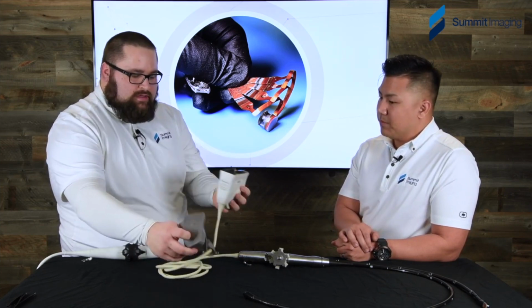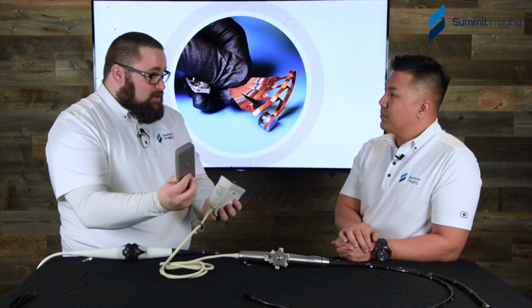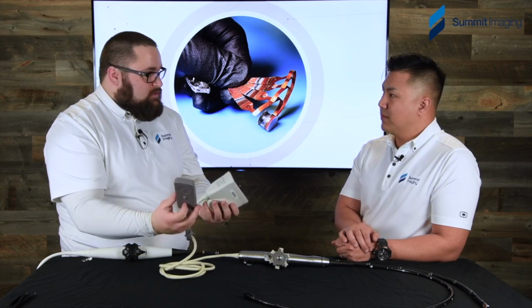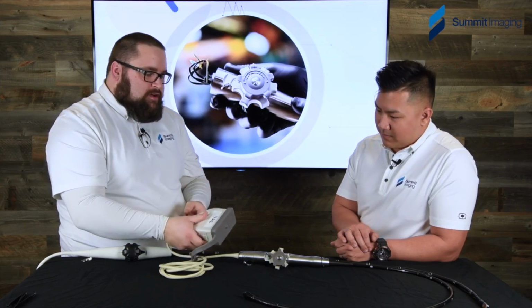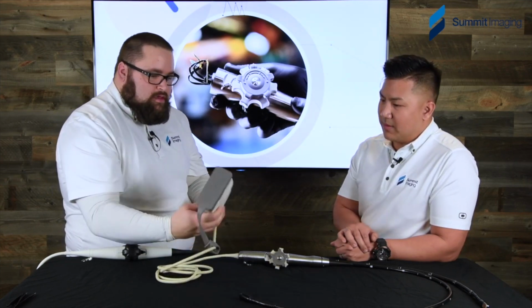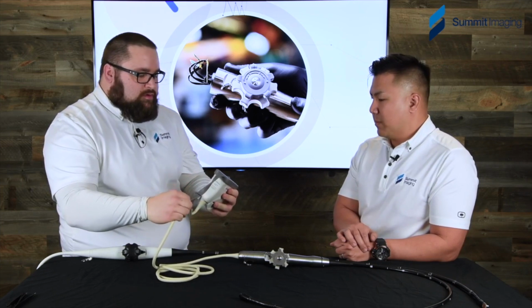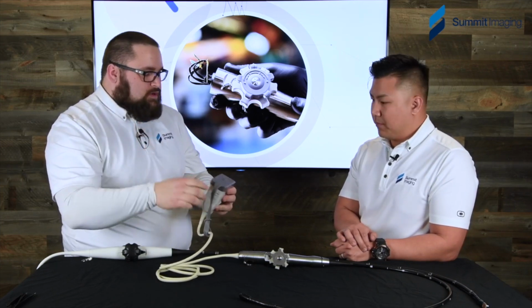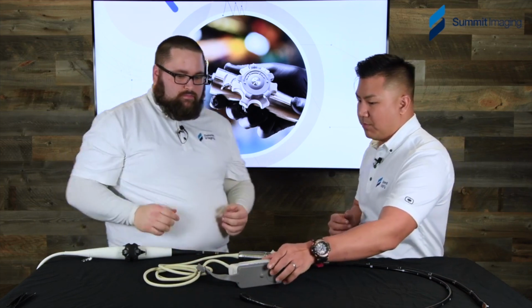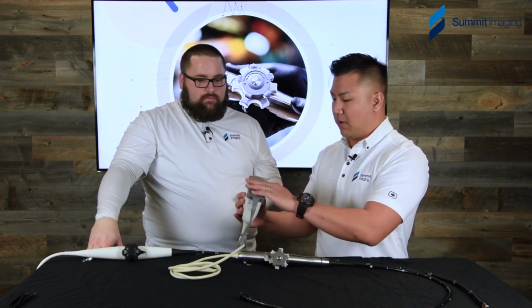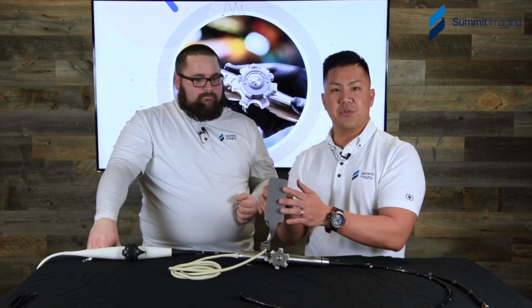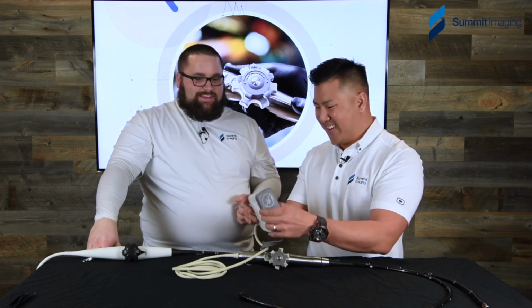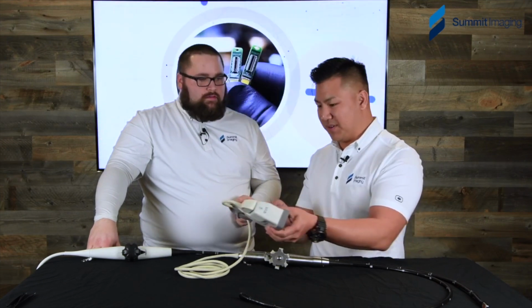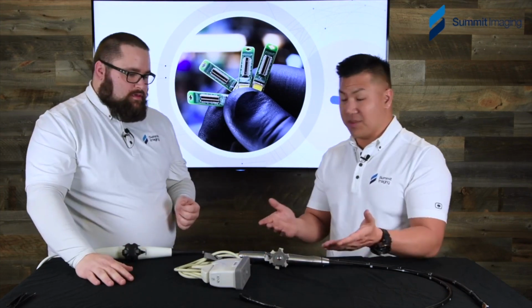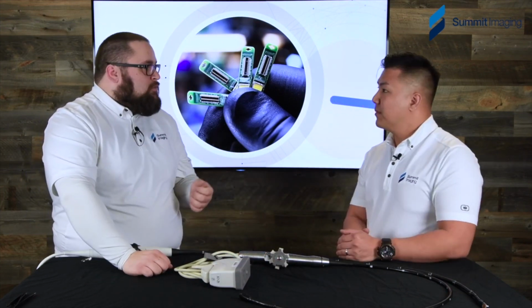And then one of the things I see happening a lot is that these little rubber covers disappear, but they actually serve a purpose. Just like when we were talking about it floating around in a bin, that is going to soften up some of those impacts to the tip. Yeah, and just having this available and not ripping it off your transducer whenever you get it is useful. And to reinforce the point, these little covers are from the OEM, and it actually says no fluid, so don't put fluid in here. That can cause some pretty serious issues for the patient and the transducer. Well, it at least gives you one more barrier protection as well.